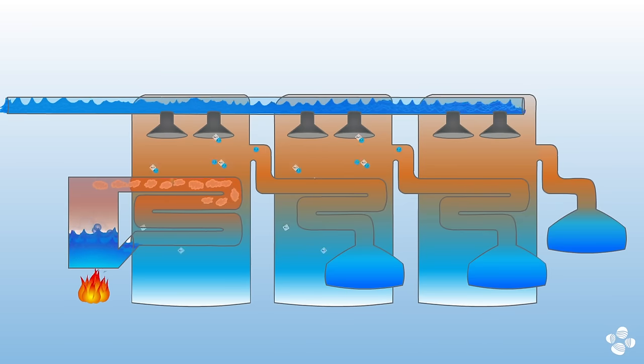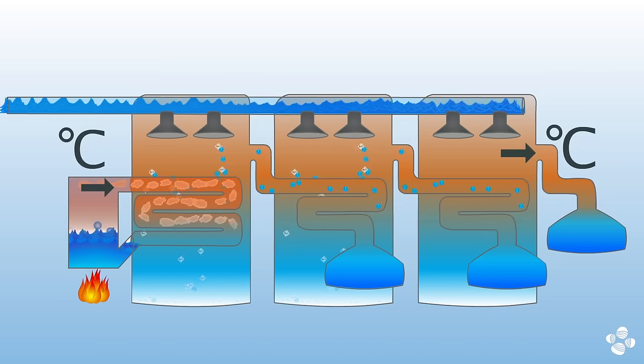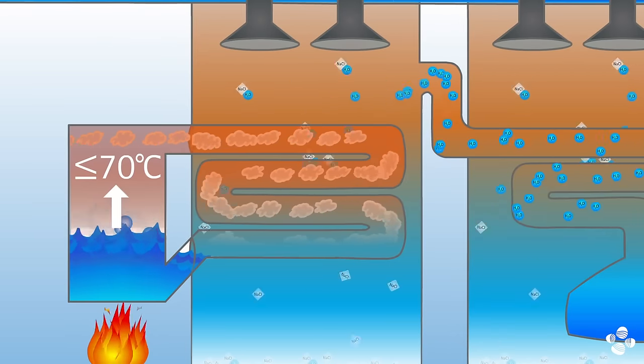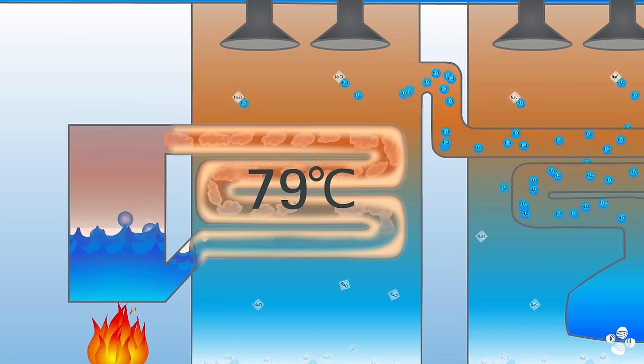Unfortunately, the process is physically limited by the first and last temperatures in the sequence. The input temperature cannot be more than 70 degrees Celsius, or minerals in the seawater will cause scaling on the pipes.